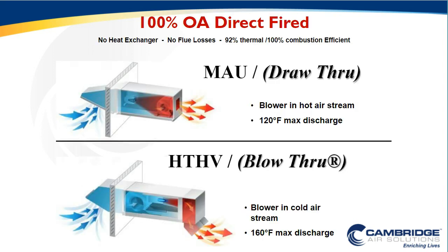So again, from a familiarity perspective, for those that may not be familiar with HTHV or direct fire technology, what is HTHV and what kinds of systems are we talking about? Many in the presentation today may be more familiar with the traditional makeup air or draw-through system, which is primarily deployed across either small kitchen systems or some industrial ventilation systems, i.e. paint booths or process exhausts. But ultimately, this technology is a 100% outside air, direct fired combustion system, meaning direct fired, there's no heat exchanger, no flue losses, such that 92% of the thermal energy in the combustion process is delivered to the space, and it's actually 100% combustion efficient, such that there is no wasted energy from the combustion perspective. All of the available energy is delivered to the space.